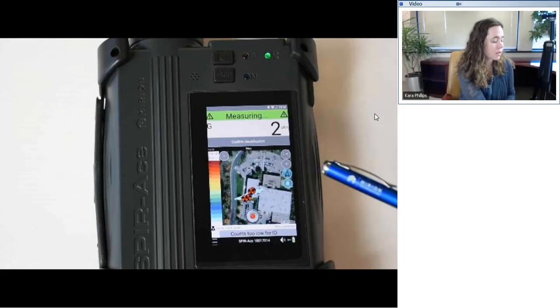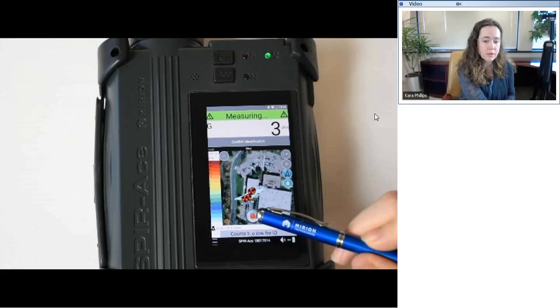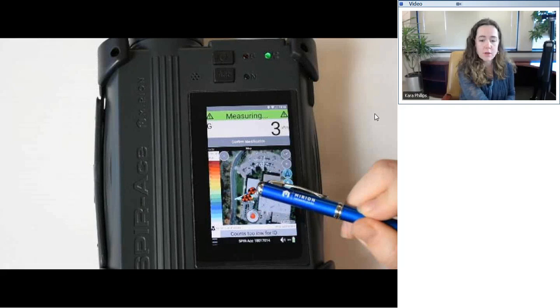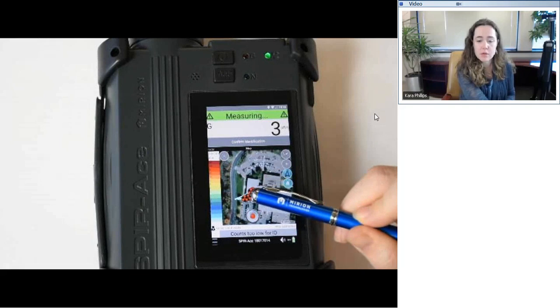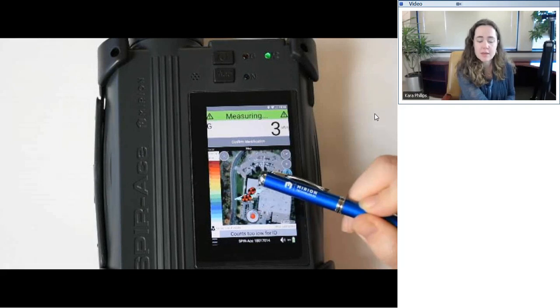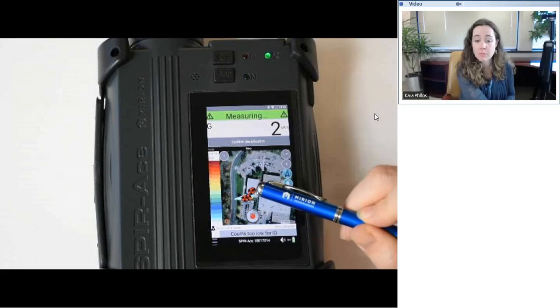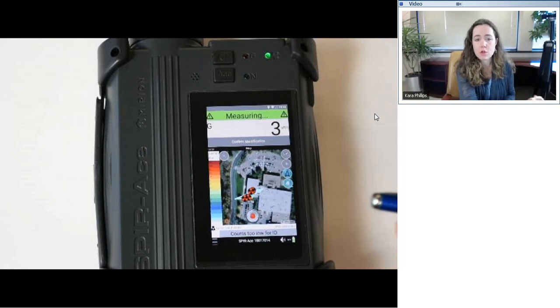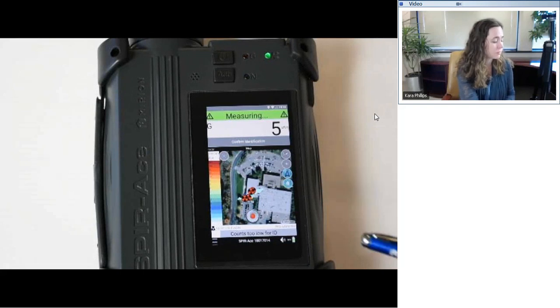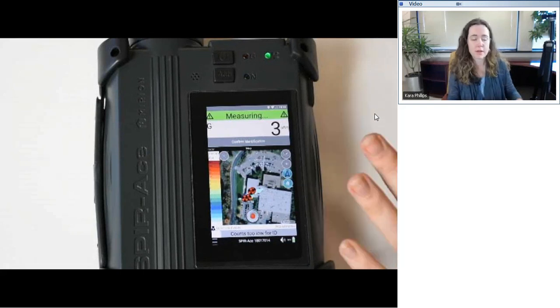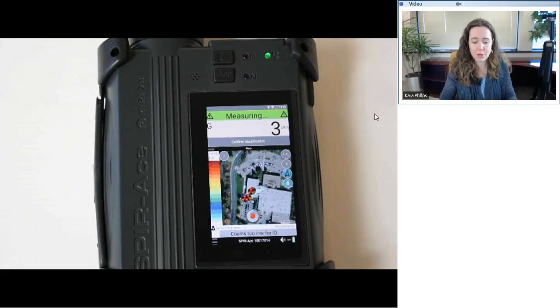And so the integrated GPS shows us the location of the devices currently. And the different radioactivity symbols here show us where the different alarms occurred over the history of this particular device until I go ahead and clear them. So this is really nice to be able to record for a particular measurement campaign where those alarms have been occurring as the operator is moving around the environment.